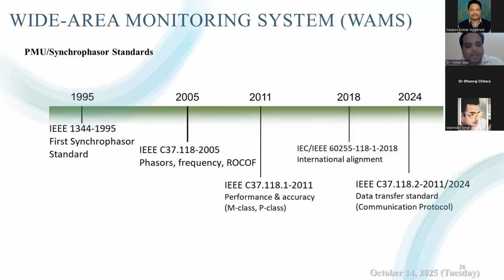Now I will also discuss something about the standards for synchrophasors. IEEE and IEC have published standards that define how synchrophasors should be measured, tested, and communicated. These standards ensure interoperability. Interoperability means the capability to communicate between devices of different manufacturers. These standards also guarantee a certain level of accuracy under both steady state as well as dynamic conditions.